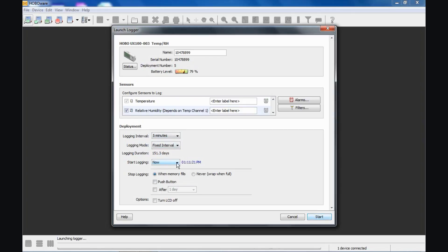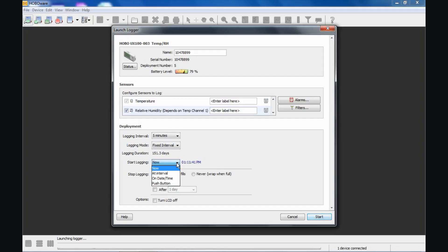Below that, we can configure the data logger as to how we would like it to start recording data. If we say now, it will start immediately when we click the start button. At interval means it will start at the next logging interval. In this case we have five minutes selected, so it will go to the next five minute increment.